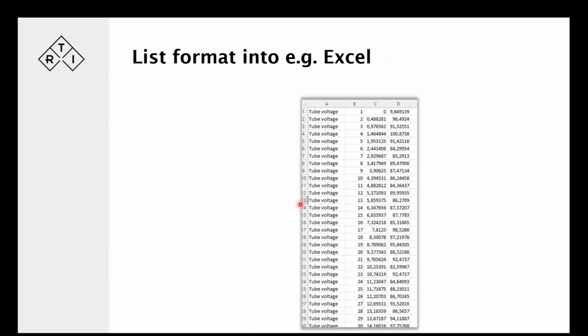where the data is exported in a format suitable, for example, for Excel, where we have each and every sample listed on a row with the corresponding timestamp and the value of that individual sample in kV. If we have a look, we can see that it starts off at 9 kV, which is pretty low. That's just when it starts to trigger, and it rises up to 96, up to above 100. Then it oscillates around 85 somewhere, and so this is where it oscillates.